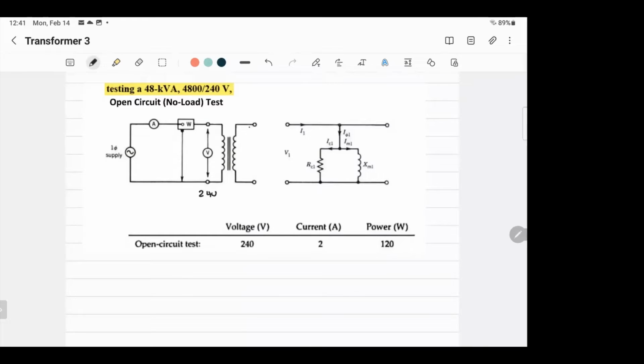How do I know that? Because when he said the voltage, the measurement is 240. That's number one. Number two, when you perform the test, you should apply the rated value. So this is the rated value of the low voltage side. So that's the low voltage side, and that's the high voltage side. So I know this is the voltage. So you just write that the open circuit voltage is equal to 240 volts, the open circuit current is equal to 2 amp, and the open circuit power is equal to 120 watts.